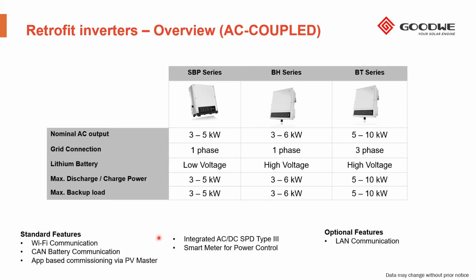In terms of what we have in the AC coupled range, we have the SBP series, which is a 3 to 5 kilowatt battery inverter. It's single phase. It's compatible with low voltage batteries, so your 48 volt batteries, like the LG Chem Resu, that's quite common in the market. As you can see, the discharge and charge power is 3 to 5 kilowatts. I must say that although the discharge power is 3 to 5 kilowatts, it's also heavily dependent on the voltage and the capacity of the battery. So you need to check whether the battery is able to also deliver that amount of instantaneous power. The backup loads as well, 3 to 5 kilowatts, you can connect on a single phase for the SBP series.